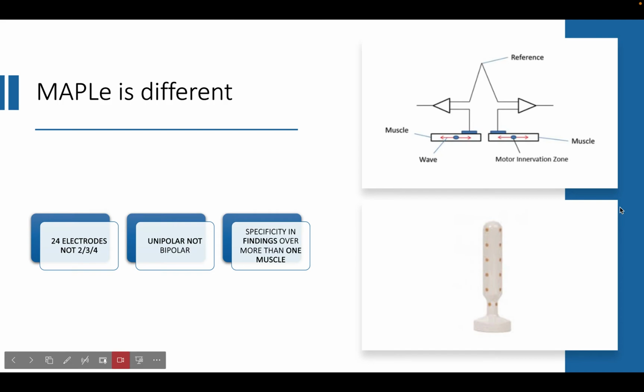So Maple is different from anything else that is available on the market at present. The finger-sized probe has 24 electrodes. Now, the standard electrodes for the current electrical stimulation or EMG biofeedback devices for the pelvic floor and sphincter quite often will have 2 large electrodes, 3 moderate-sized electrodes, or 4 smaller electrodes. There are no other devices with a probe that has the size of the Maple, the length of the Maple, and the number of electrodes as the Maple. So that's one way that it is different from other devices that are available in the UK, especially at the moment. Its method of use for assessment and treatment, especially for EMG functions, is very different from what is available on the market at the moment.